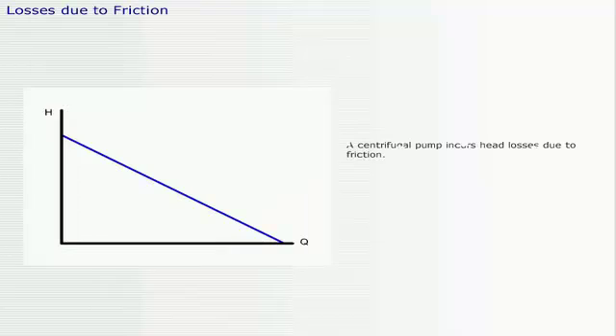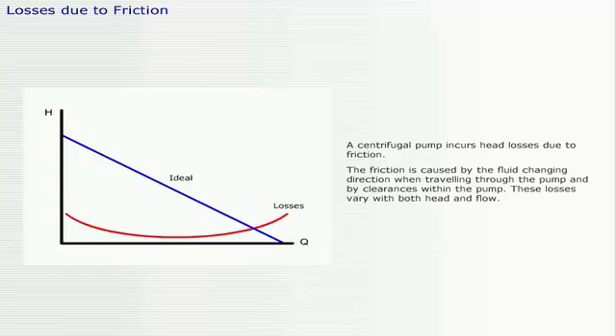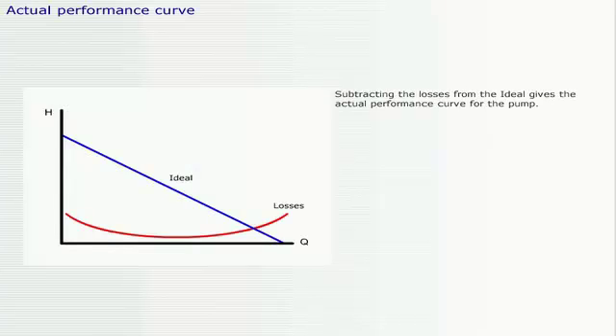A centrifugal pump incurs head losses due to friction. The friction is caused by the fluid changing direction when traveling through the pump, and by clearances within the pump. These losses vary with both head and flow. Subtracting the losses from the ideal gives the actual performance curve for the pump.